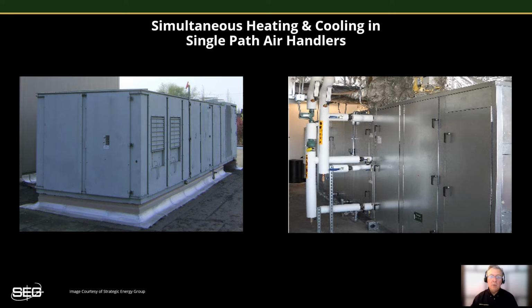In our last video, part 1 of simultaneous heating and cooling, we mentioned how some of the older HVAC systems were actually designed to always operate heating and cooling simultaneously. But most buildings constructed within the last 40 years or so tend to utilize what are known as variable air volume, single path air handlers for their HVAC systems. These air handlers tend to be much more efficient as they're designed to temper only a single stream of air that gets either heated or cooled. They feed the conditioned air out to the various zones of the building at a temperature chosen to provide air just cool enough to keep their zones from overheating.